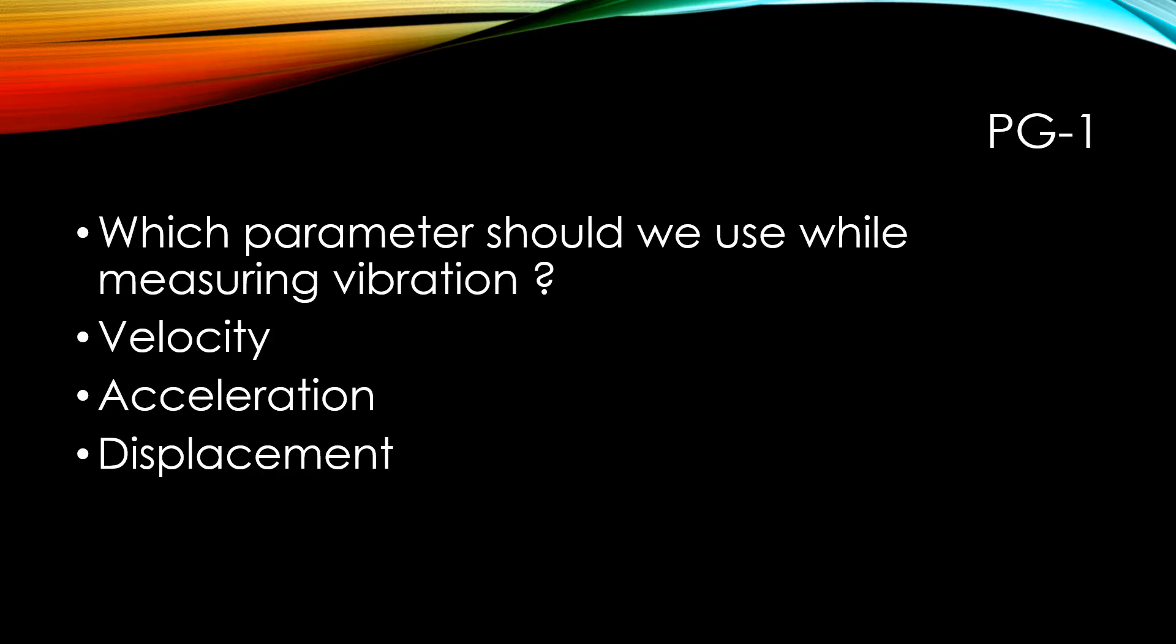In the case where there is a high frequency range, the acceleration values yield more significant values than velocity or displacement. Hence, for the frequency over 1000 Hertz or 1500 Hertz, the preferred measurement unit for the vibration is acceleration.